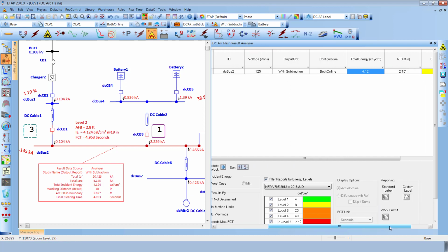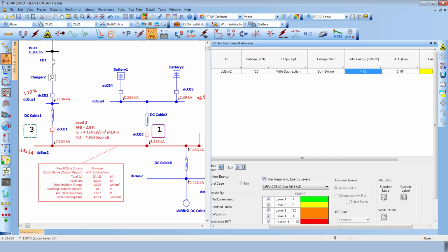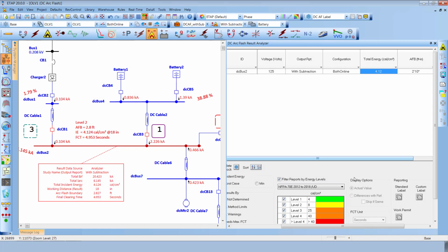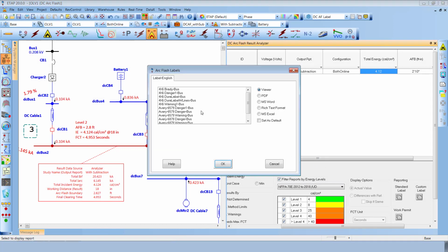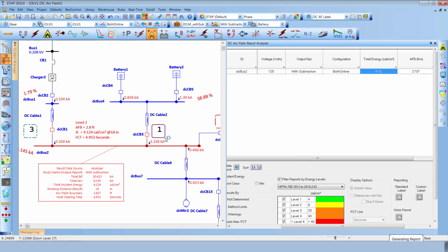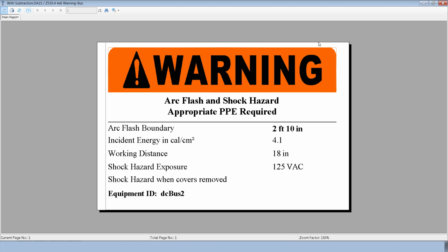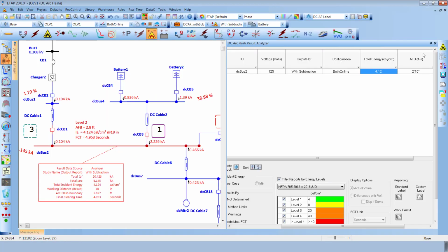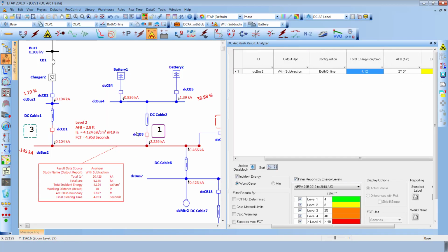ETAP also supports another deliverable using the standard and the custom labels, which can be generated after running all the possible configurations and scenarios and still determine the worst case incident energy that can happen in this particular fault location at each stage. It can be used as a sticker depending upon proper engineering judgment, and also accounting for it without even setting it up in ETAP projects.